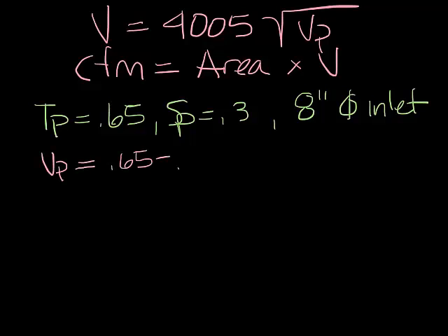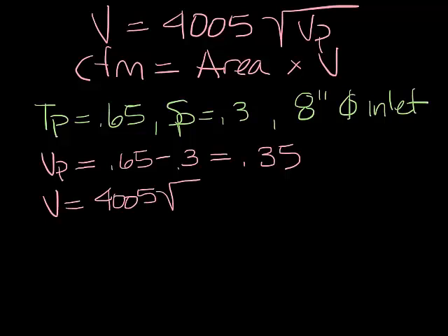So you know the velocity pressure is 0.65 minus 0.3, which is 0.35. So the velocity is 4005 times the square root of the velocity pressure. Now if you work that out, you come up with a velocity of 2369 feet per minute.